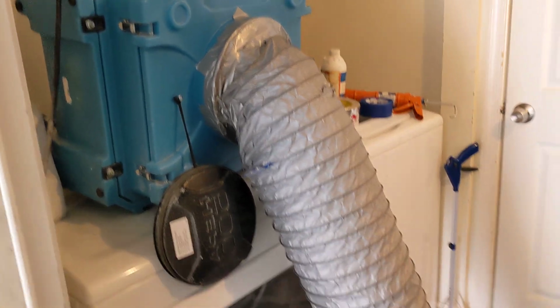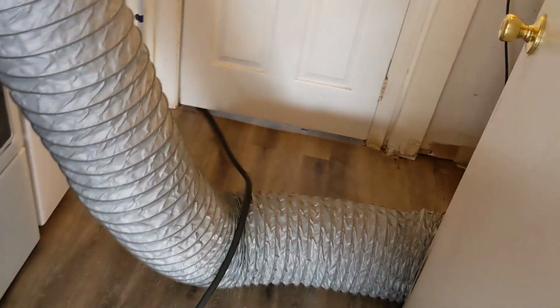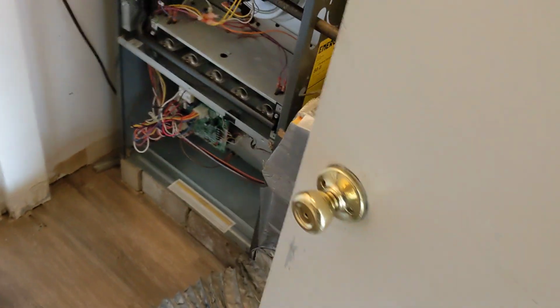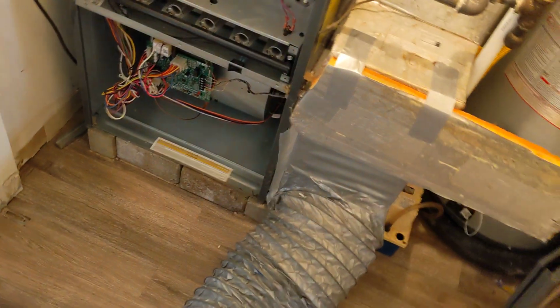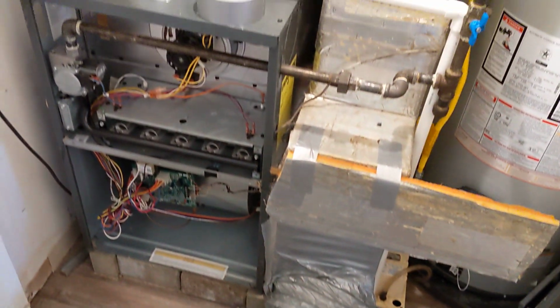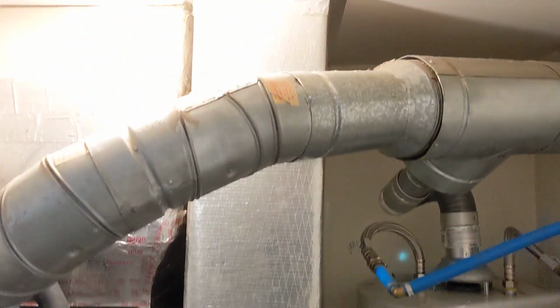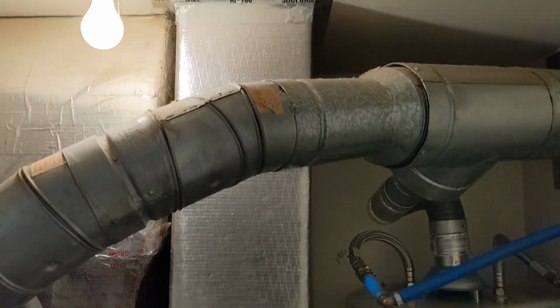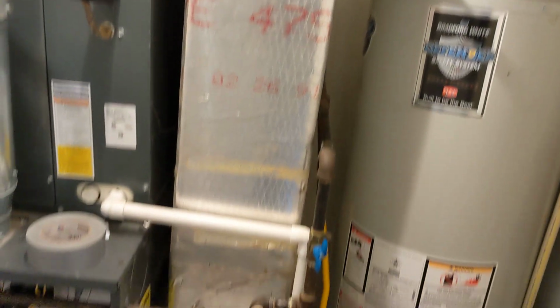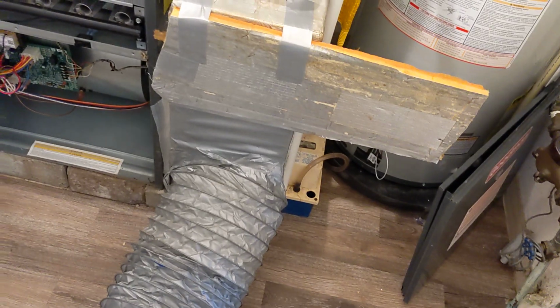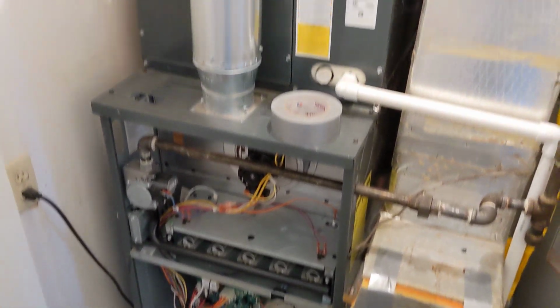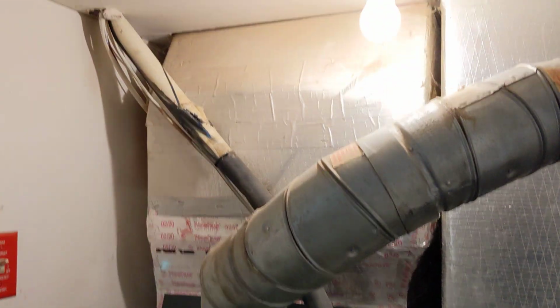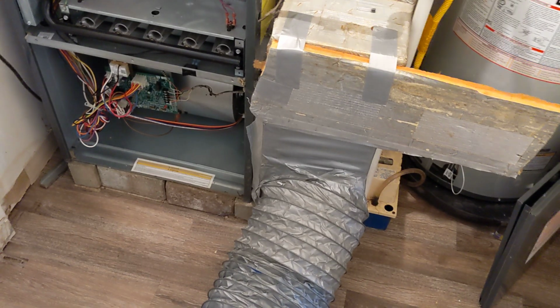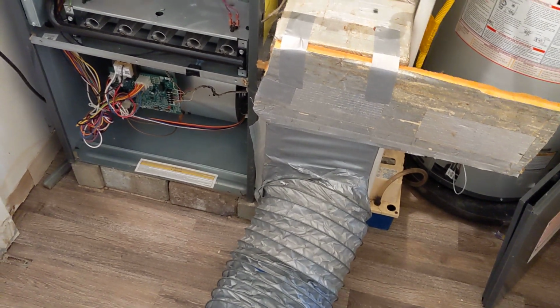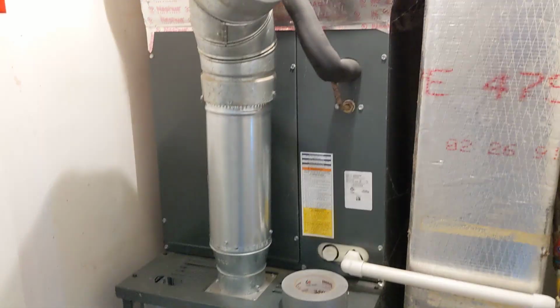And we have that ductwork connected to the unit itself. So this is the return side of the unit right here that goes up on the right side of your screen. That's the return side. Then this is the supply side. And then goes up. So whenever we're doing duct cleaning, we always start with the return side first. So you always do the return, then the unit itself, then the supply.